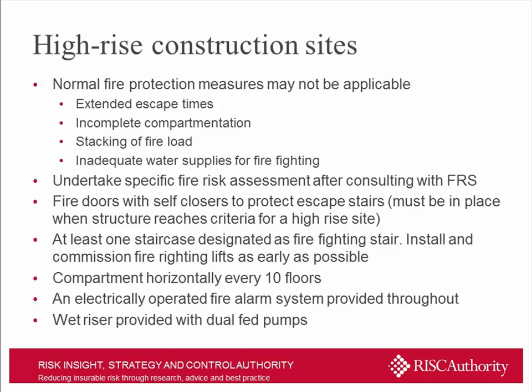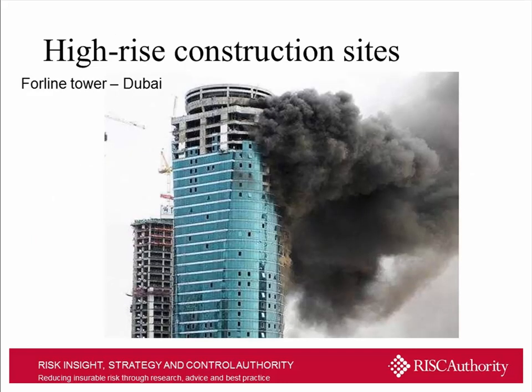And wherever possible, if you have protection systems that are meant to be installed, that they're installed as early as they possibly can be. An example there of a fire that happened in Dubai during the construction phase. Got a couple more examples of fires in Dubai, sadly, coming up in a few moments. But the building, as you can see, wasn't finished. The fire started in a shaft that ran up the full height of the building, and somehow waste packaging became involved, or it was ignited.